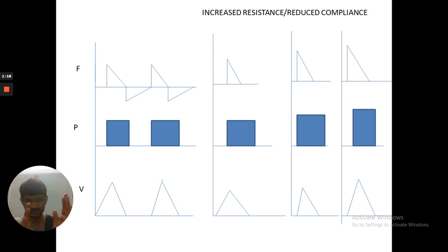When the resistance is increased, the flow and pressure gradually increase, but with that flow and pressure, the tidal volume delivered will be low. Gradually the flow and the pressure increase, and the tidal volume reaches the set point. The flow and pressure will increase till the tidal volume is achieved. You can see gradually the flow and the pressure are increased till the desired tidal volume is achieved. That is a major difference between volume control and pressure control.